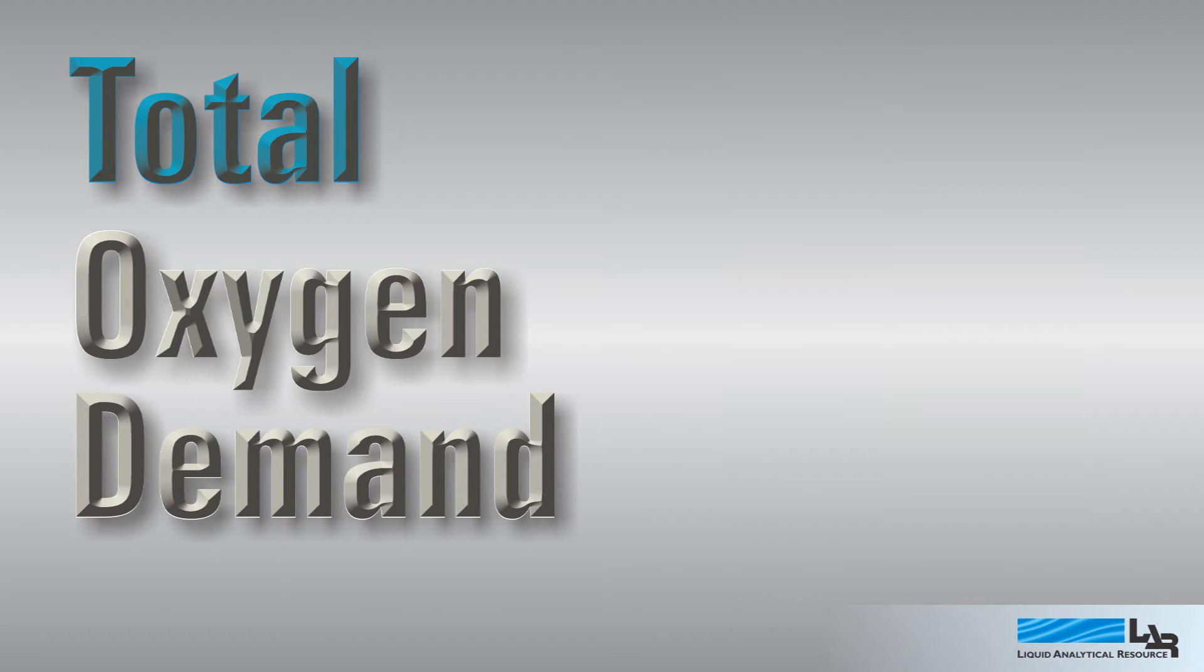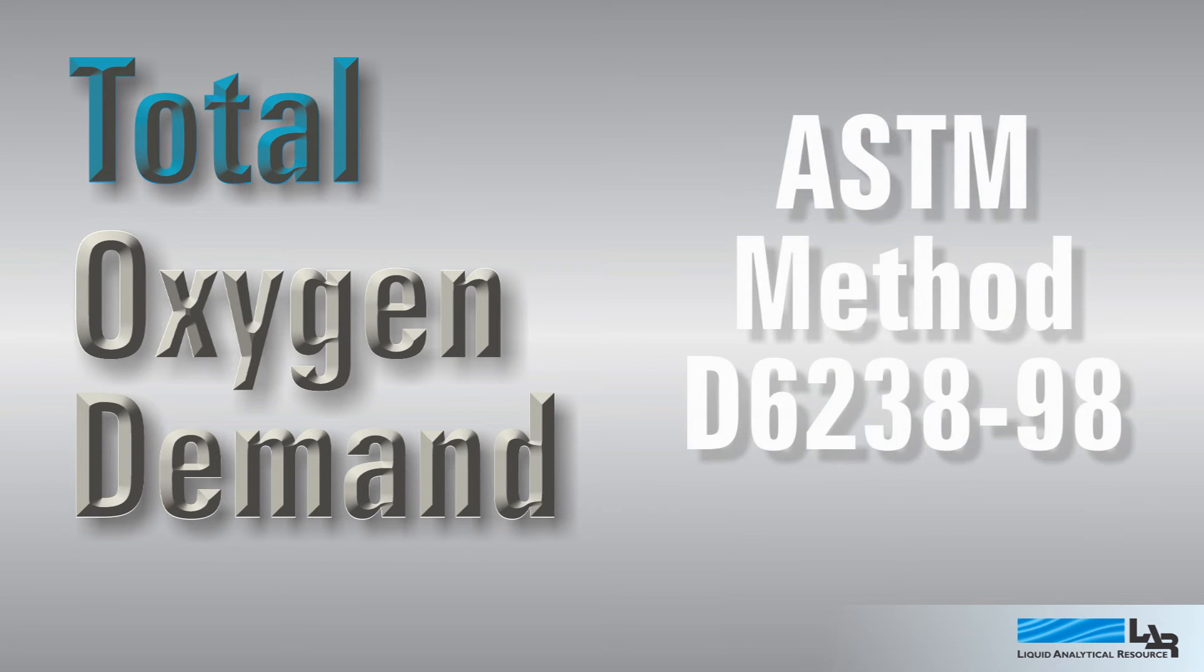Total oxygen demand doesn't depend on microbes or chemicals. Instead, the sample is oxidized quickly, cleanly, and completely using only high temperature, and the resulting oxygen depletion is easily measured with an O2 gas detector without toxic reagents or chemicals of any kind.